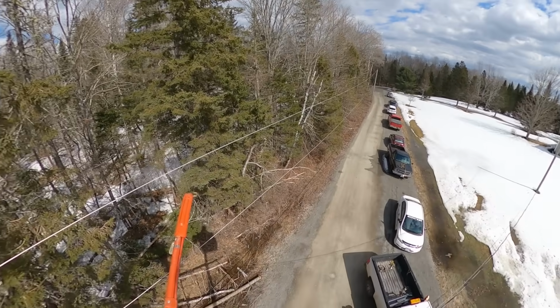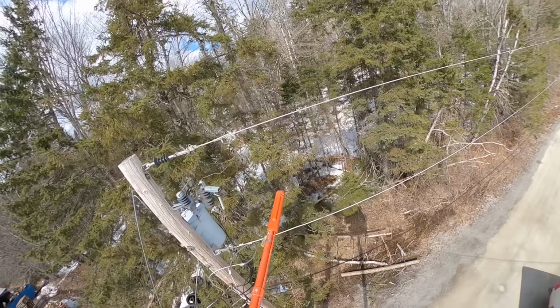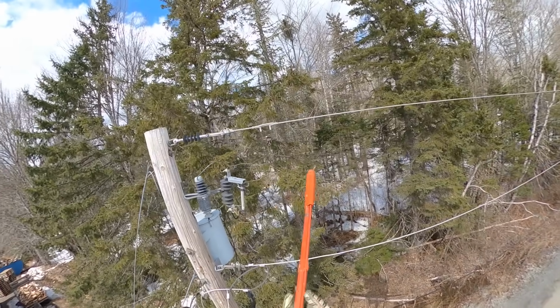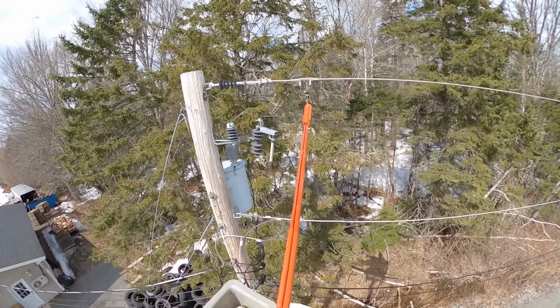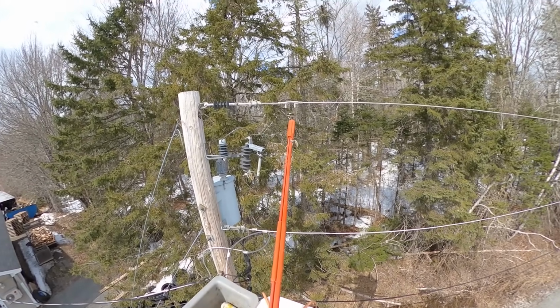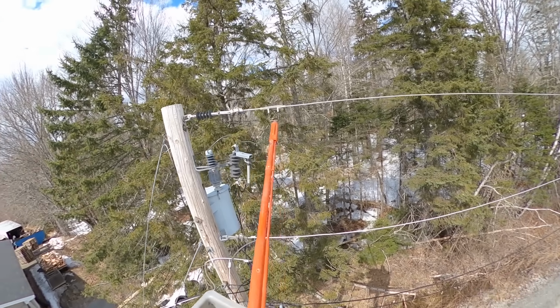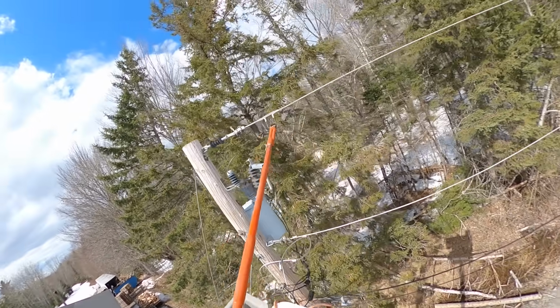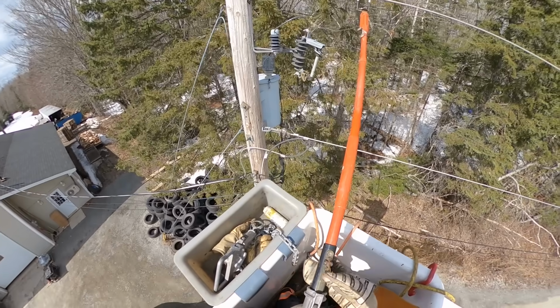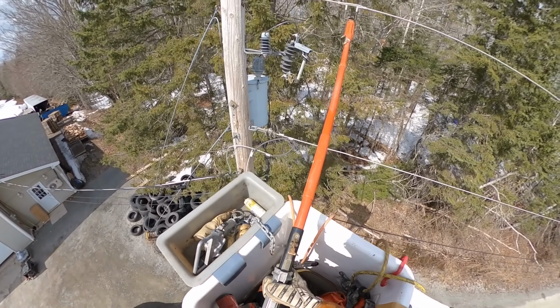Now, the reason I left that tap clamp on loose instead of using a screwdriver or wrench to tighten it is they're pretty easy to over tighten. When you use your grab-all to tighten these guys up, pretty well as much force as you can get twisting it, it's still going to come off. If you put a wrench on that, when the guy comes with the hot stick to remove it, it might not be doable.